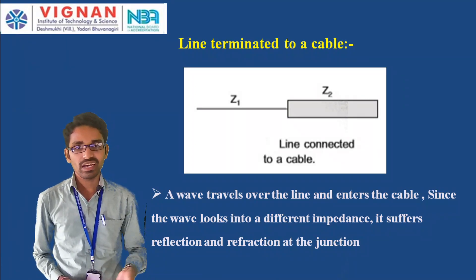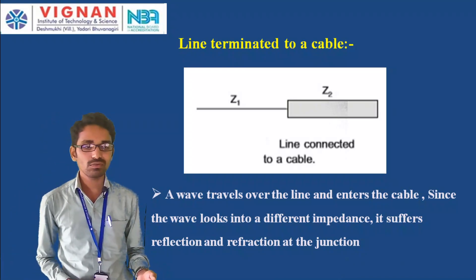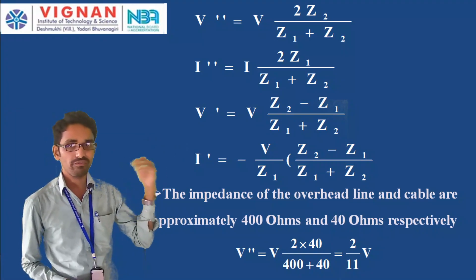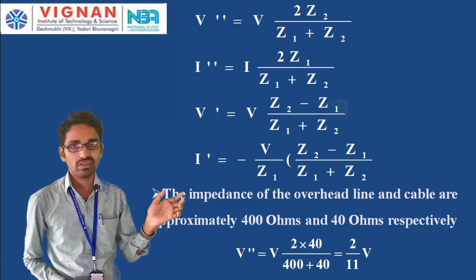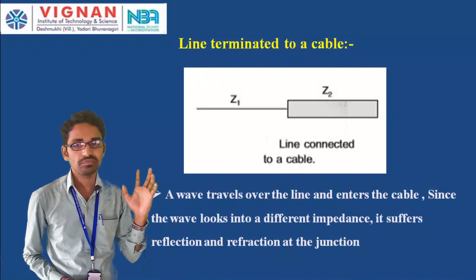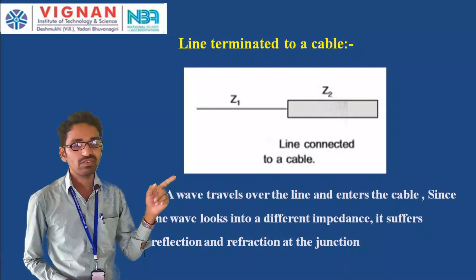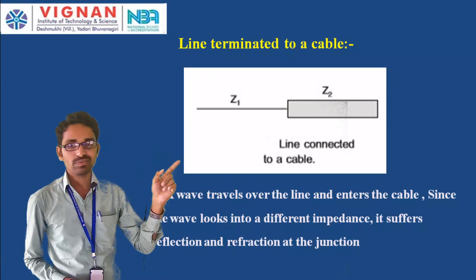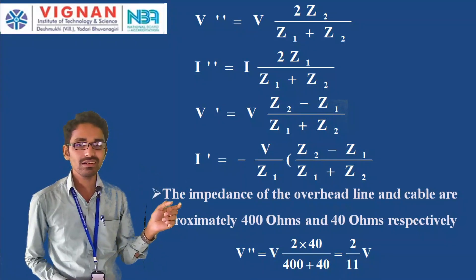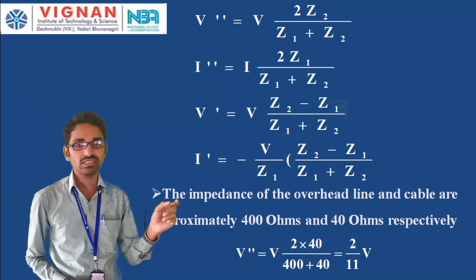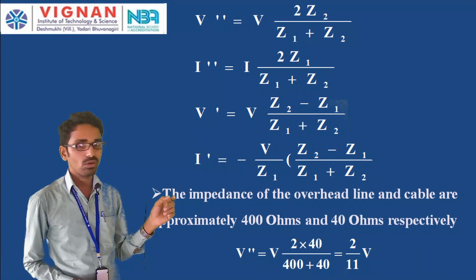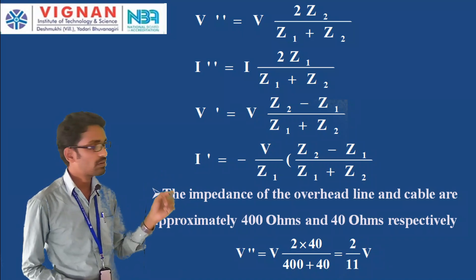At the junction, the refracted voltage V'' equals V × 2Z₂/(Z₁+Z₂), the refracted current I'' equals I × 2Z₁/(Z₁+Z₂), the reflected voltage V' equals V × (Z₂−Z₁)/(Z₁+Z₂), and the reflected current I' equals −(V/Z₁) × (Z₂−Z₁)/(Z₁+Z₂), where Z₁ is the surge impedance of the transmission line and Z₂ is the surge impedance of the underground cable.